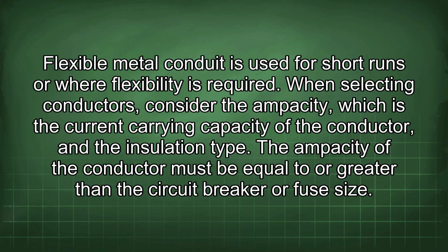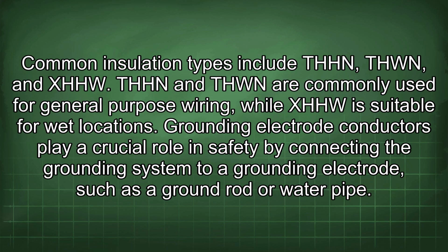When selecting conductors, consider the ampacity, which is the current carrying capacity of the conductor, and the insulation type. The ampacity of the conductor must be equal to or greater than the circuit breaker or fuse size. Common insulation types include THHN, THWN, and XHHW. THHN and THWN are commonly used for general-purpose wiring, while XHHW is suitable for wet locations.